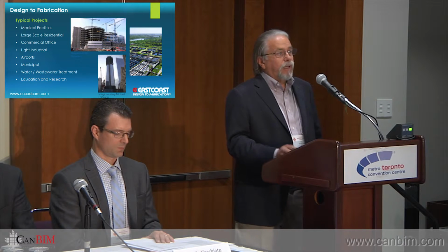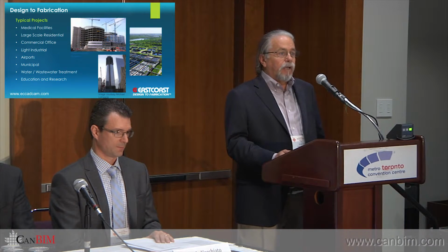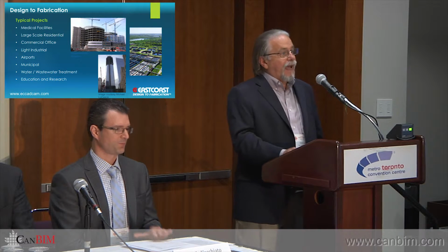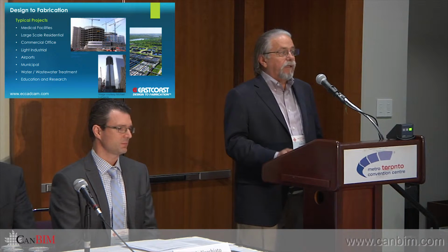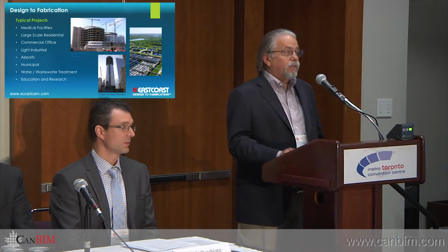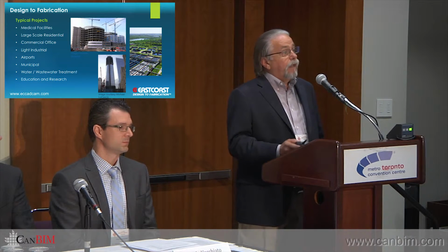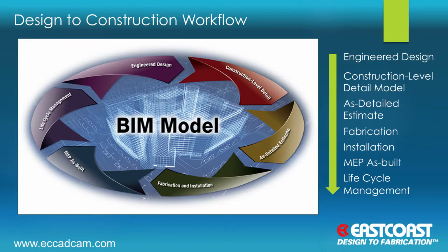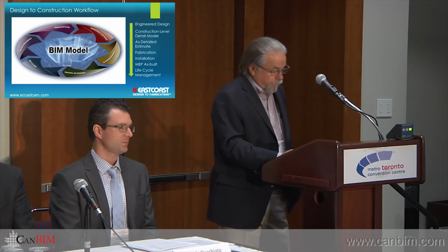After analyzing the emerging trends in design to construction, we can also take these Revit models and bring them into AutoCAD MEP, assigning real manufacturer content and real specifications as it's imported into AutoCAD MEP. Apply all the hanger information, pick up all your Trimble points, and then send that directly back into Revit to make it a Revit deliverable or an AutoCAD MEP deliverable, whichever suits the purpose.